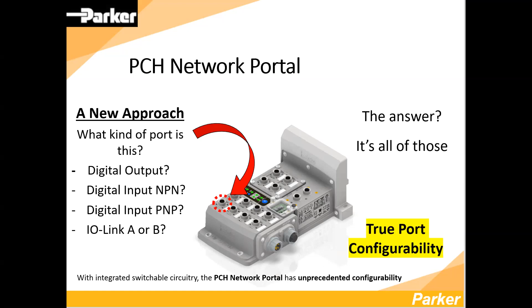Some features we like to talk about: we've tested this in welding applications, and the housing itself is splatter resistant. You get electric and pneumatic zoning with this, which I'll touch on more in a second. It's safe power capable. This is not a safety device, it does not have a safety rating, but it's safe power capable. That means your input or logic power is galvanically isolated from your output or auxiliary power, which is required when you've got safe and non-safe power that don't share a common. It can also handle test pulses of safety circuits, which is why we call it safe capable.